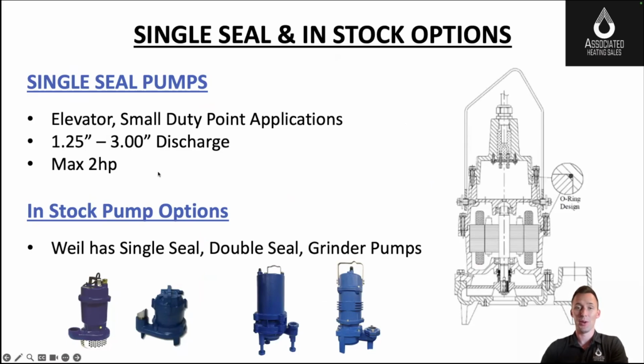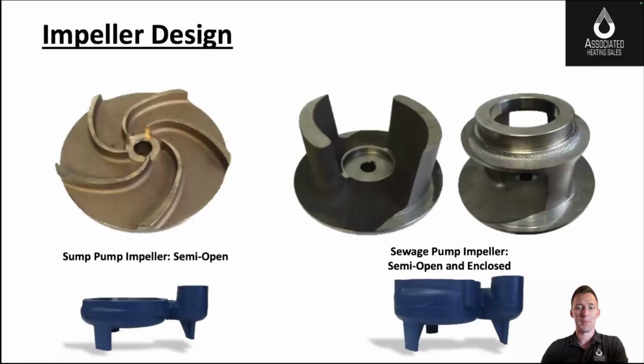If you're in a scenario where you need an in-stock pump, Weil has some in-stock pumps as well. They might go into an elevator just fine. So let us know. Elevators are typically, if you're doing 50 gallons a minute, 1/2 horsepower pumps might work quite well. We'll get into a little bit about the differences between a sump pump, so just groundwater, versus applications where you're pumping sewage. So you have sewage systems.